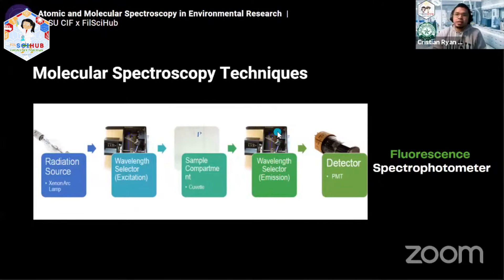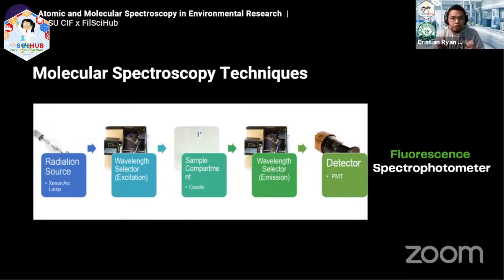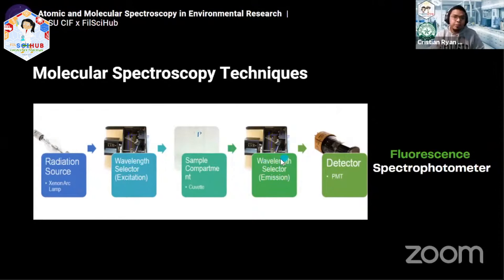We have two wavelength selectors because for fluorescent samples — when we say fluorescence — if earlier the target was a chromophore, now when the sample has a fluorophore, after it absorbs light, it also emits light later on. That emitted light is what the machine detects, so you also need to filter the emitted light of your sample. That's the concept of fluorescence.